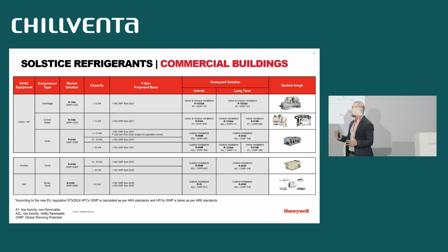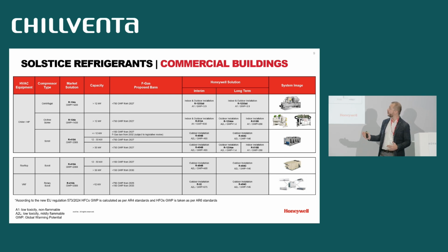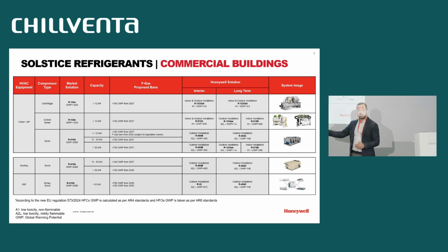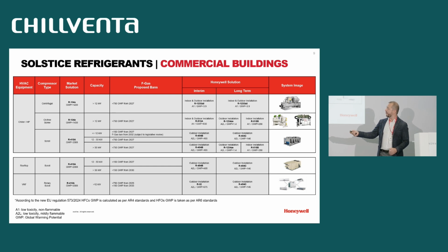So some equipment types will not be able to use refrigerants above 750 GWP. From 2027, for example, above 12 kilowatts in chillers and heat pumps, whereas below 12 kilowatts will not be able to use any refrigerants above 150 starting from 2027. Coming to rooftops and VRFs, we see a similar tendency where 410A refrigerants will be replaced with lower global warming potential refrigerants, starting from 2027 up to 50 kilowatts, and above 50 kilowatts, there will be a change again to below 150 starting from 2030.